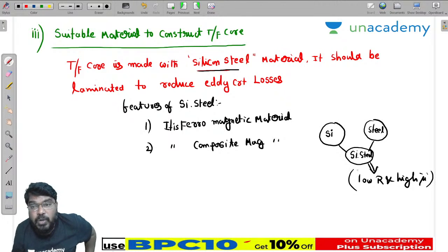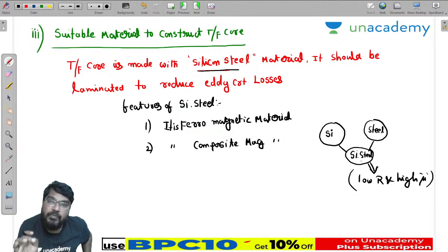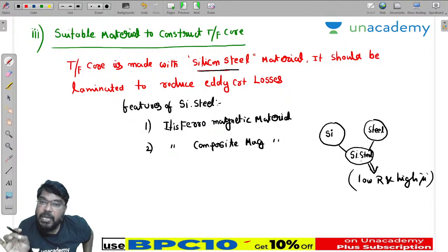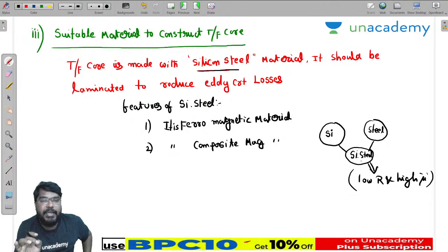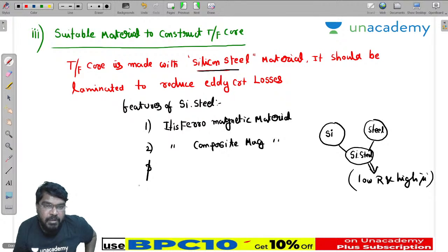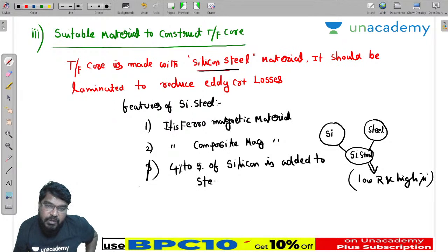So how much is the composition? For example, we may get a question on the percentage of silicon in the steel material. The answer is 4 to 5% — silicon is added to the steel material to reduce the eddy current losses.